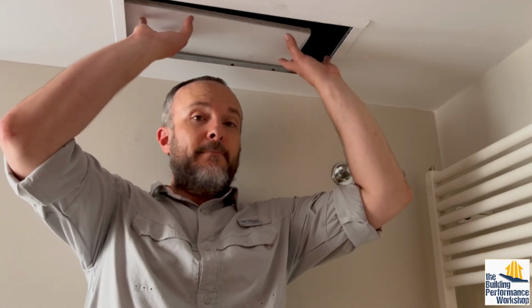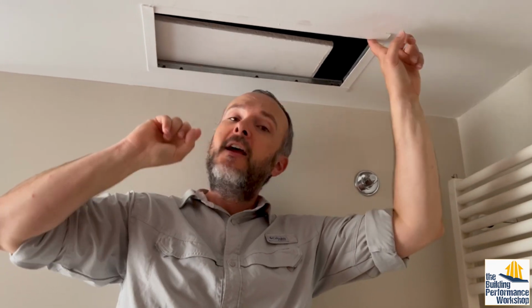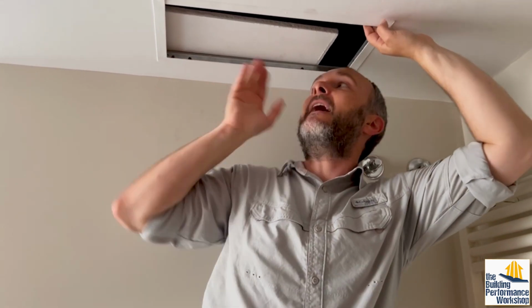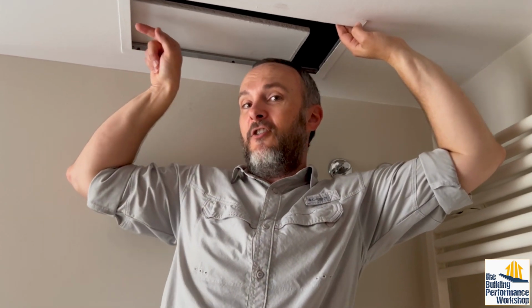Now, what this means, that this is the only access hatch we've got, is number one, your filters are probably not going to get cleaned or replaced because it's so hard. I can stick my head and one arm up in here, but I'm not positive that I'm going to be able to reseat that filter correctly all the way down there. So if I'm a professional, I'm going to be very nervous, and I might just use a vacuum and do a light job with it.